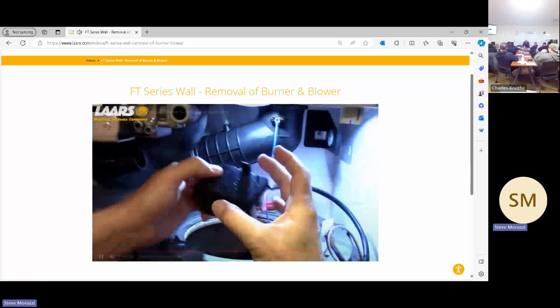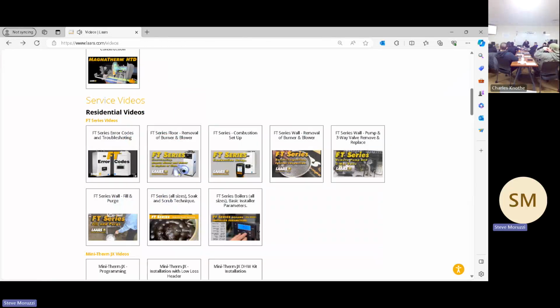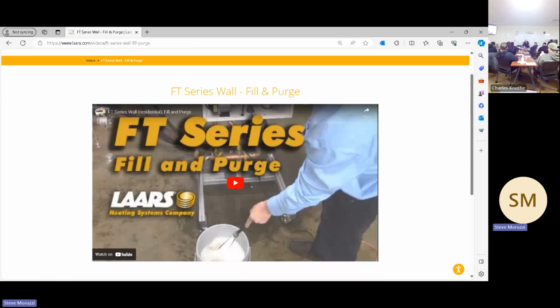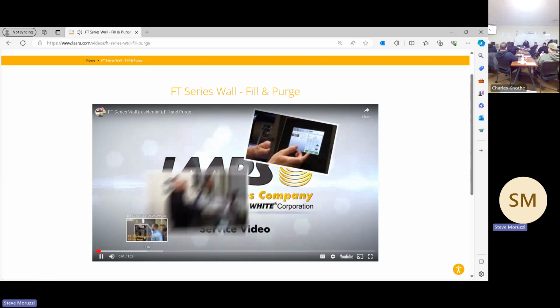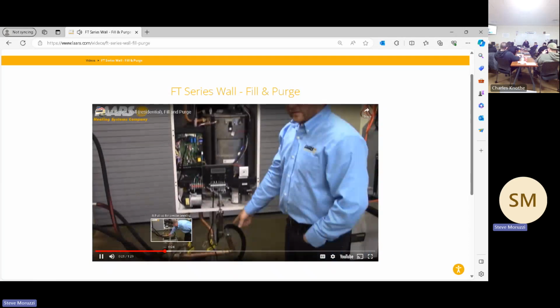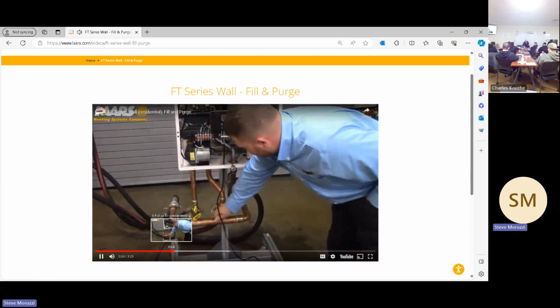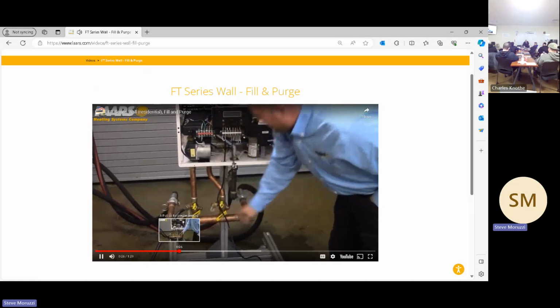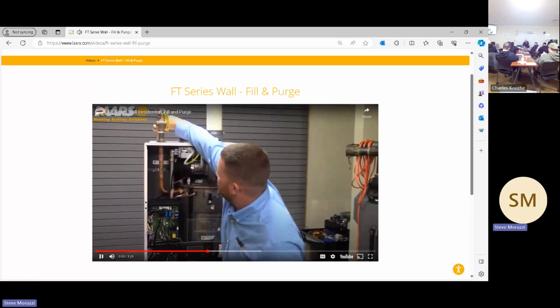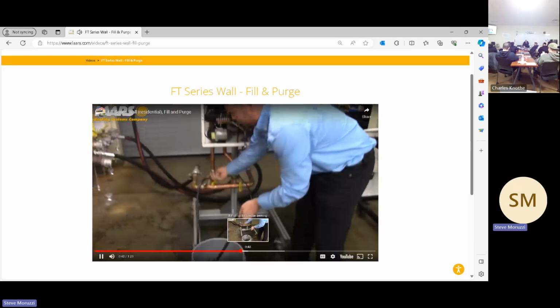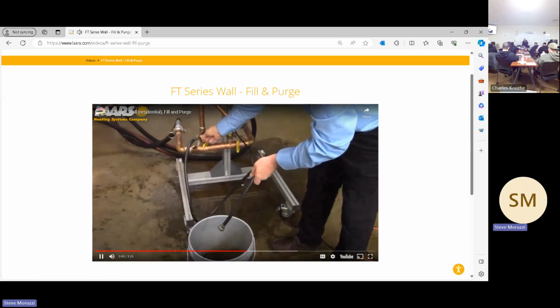What else do we have in here? How to pull the pump and three-way valve. How to fill and purge the system. When I talked about you need to give it a TT demand, if you're trying to purge these wall hungs with a diverter valve, Mike showed that he can't get any water coming out of this until he gives it a TT demand. Once he gives it a TT demand, then he can flush that air.